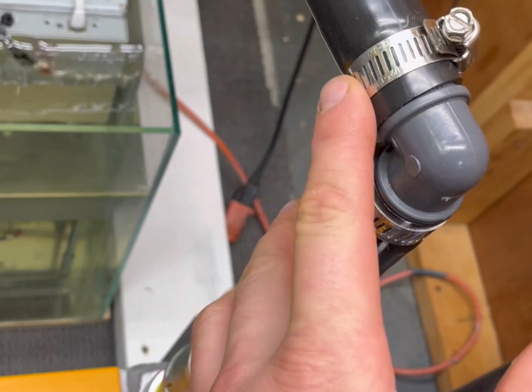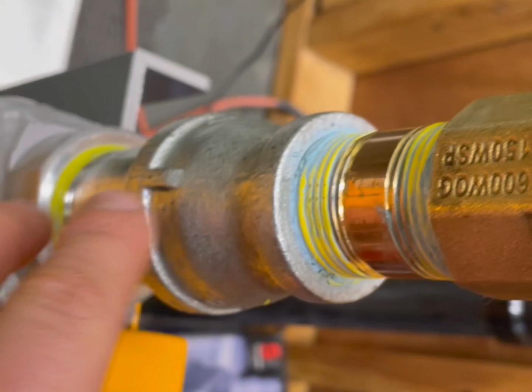When I first did these joints I used 3/4 inch plumbing, right now I'm running 1 inch plumbing. Dielectric fluid really has a way of finding its way out, and you'll get leaky seals if you just use white tape, no matter how good you tape it. So what I ended up doing is using gas tape, because the threads are a little more coarse. You can use all brass, but I used galvanized here because they didn't have the size I was looking for at the time. It's not a big deal, but brass is a little bit better, of course.